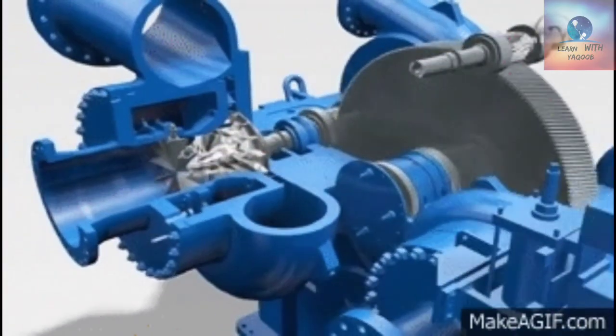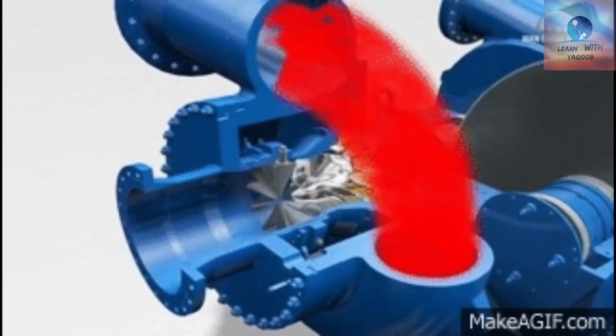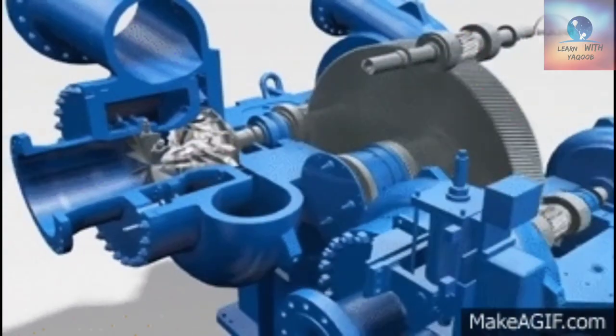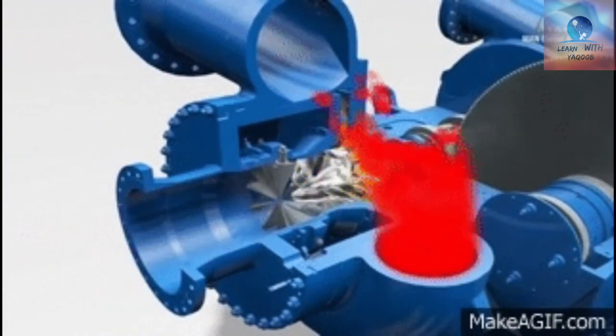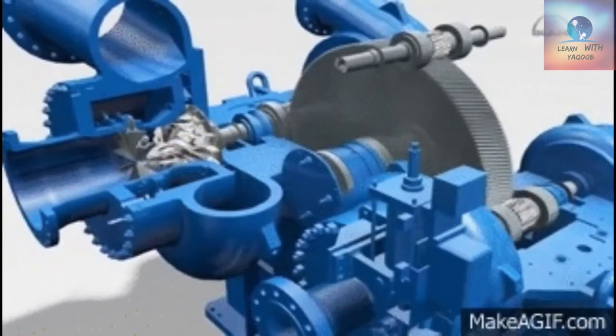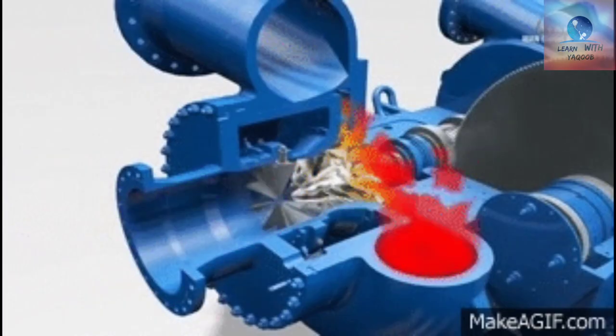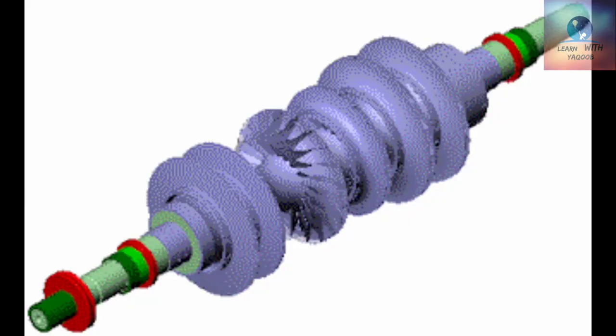Almost identical in construction to centrifugal pumps, centrifugal compressors increase the velocity of gas by throwing it outward by the action of a spinning impeller. The gas expands in a casing volute where its velocity slows and its pressure rises. Centrifugal compressors have lower compression ratios than displacement compressors, but they handle vast volumes of gas. Many centrifugal compressors use multiple stages to improve the compression ratio. In these multi-stage compressors, the gas usually passes through intercoolers between stages.